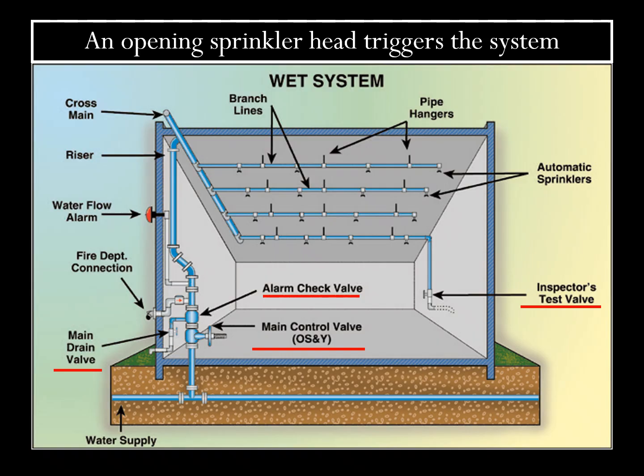Friends, in this diagram, the operational point of working of a wet sprinkler system is explained. Let us start. There is a vertical riser system here, and it has got a fire inlet connection, a water flow alarm, and from this riser system are connected the cross mains, horizontal arms, maybe on one side or both sides, and these are the sprinklers here. These are the branch lines. This is the cross main. It may have different types of formations.